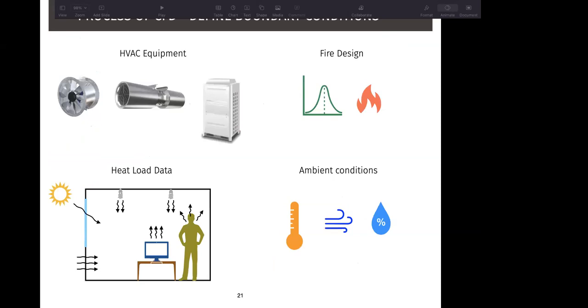The 4th kind of boundary condition that can be applied to a problem is ambient conditions, which means your dry bulb temperature, your wind conditions, the humidity to be considered. So ISHRAE gives you the climatic condition for each station in India. It will give you the hottest month. In this case, for Bengaluru, it's April, with the peak annual DBT for n equals to 50 years as 38.4 degrees centigrade and wet bulb temperature as 29.6.